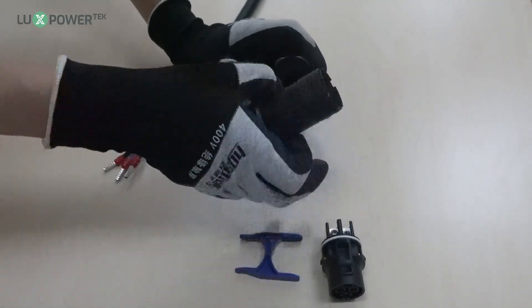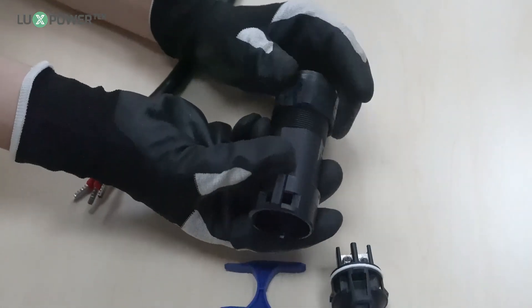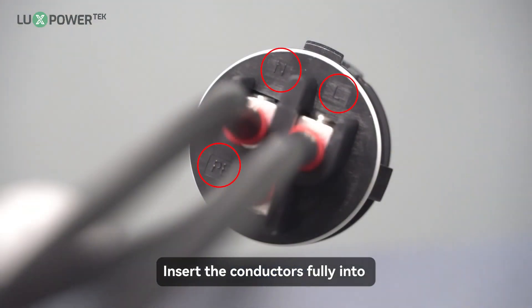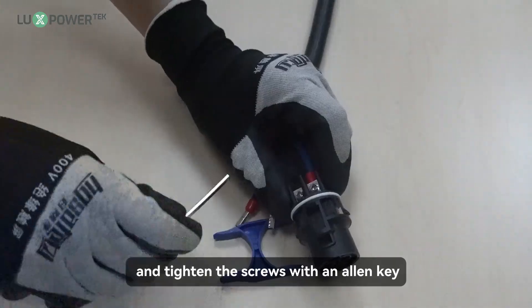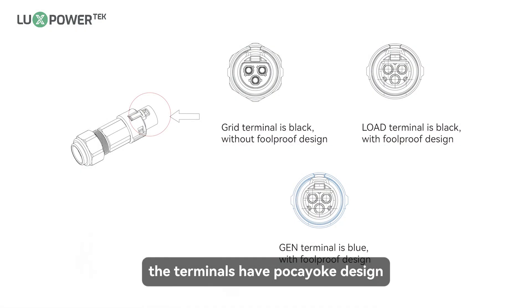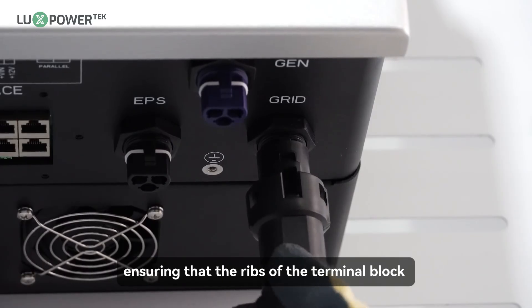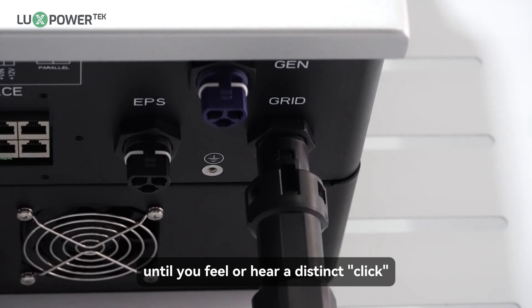Step 3: assemble the gland. Step 4: thread the AC cable through the cable seal and socket. Insert the conductors fully into the corresponding terminals of the terminal block and tighten the screws with an Allen key. The terminals have a poka-yoke design; please refer to the image to ensure correct AC cable connection. Assemble the grid connector, ensuring that the ribs of the terminal block and the grooves on the housing are fully engaged until you feel or hear a distinct click.